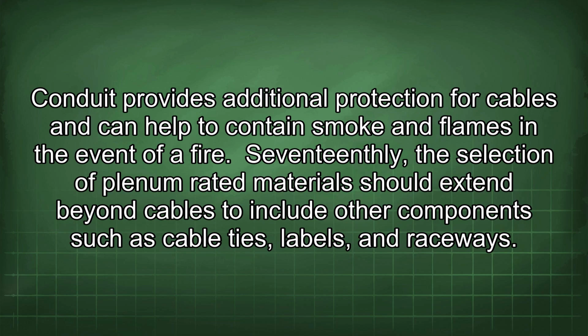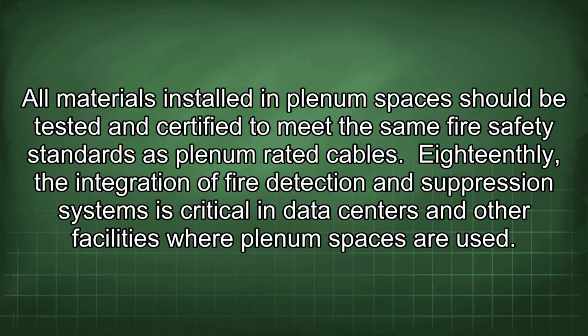17thly, the selection of Plenum-rated material should extend beyond cables to include other components such as cable ties, labels, and raceways. All materials installed in Plenum spaces should be tested and certified to meet the same fire safety standards as Plenum-rated cables.